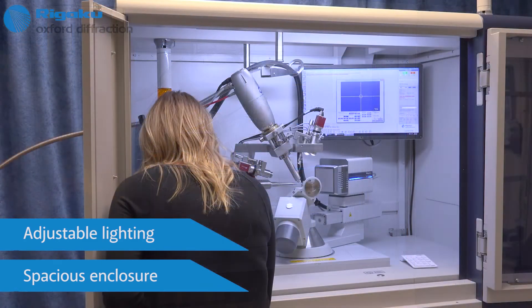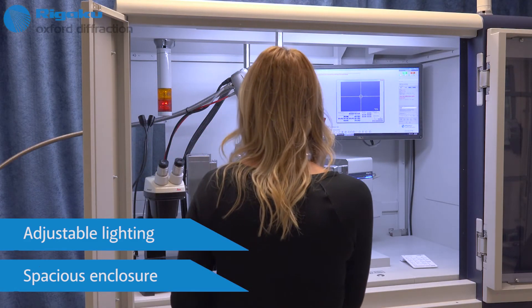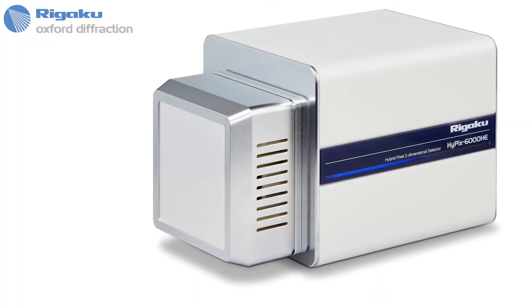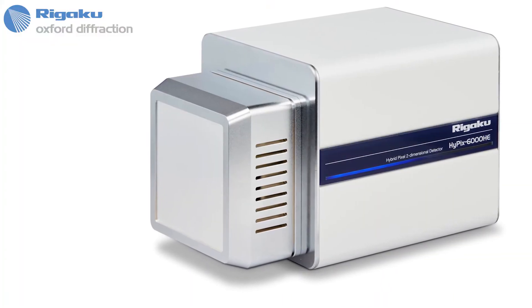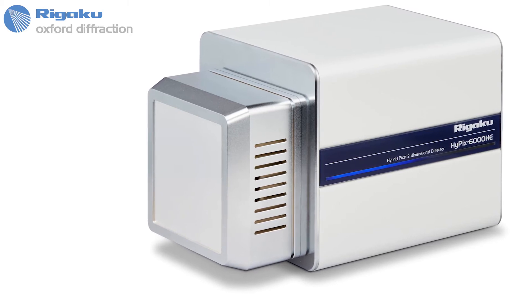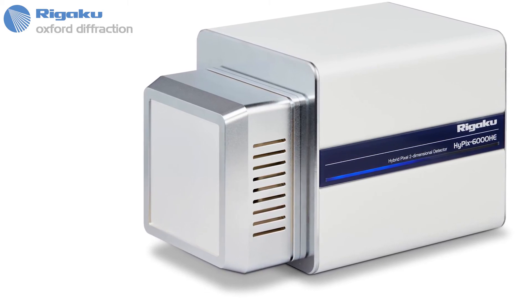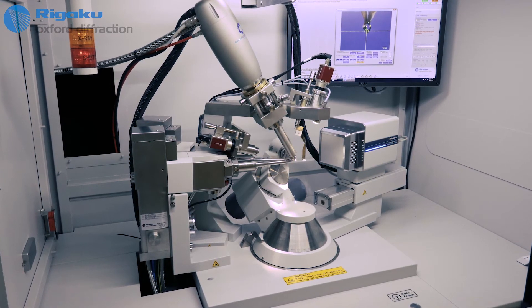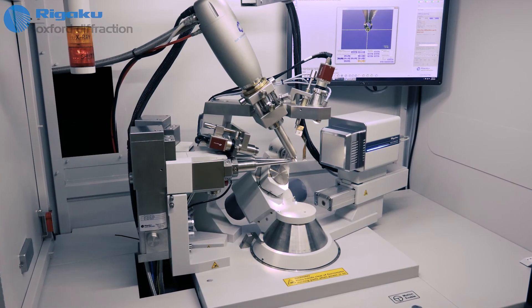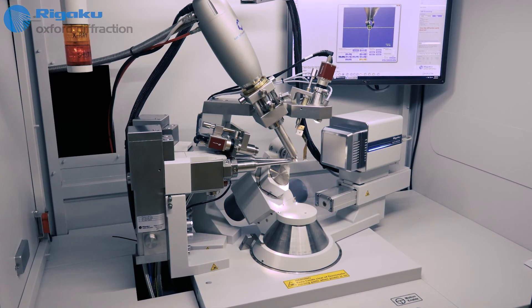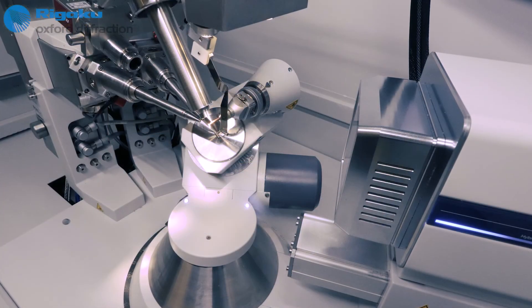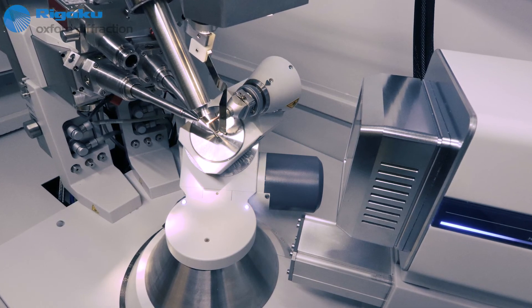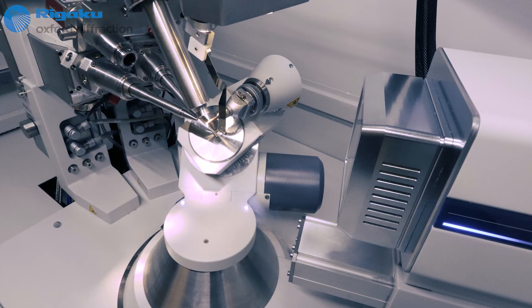Rigaku's XtaLAB Synergy systems are equipped with a hybrid photon counting detector, the HyPix-6000HE, which combines small 100 micron pixels with a zero dead time mode and a lightning fast 100 Hz frame rate, providing the user with the ability to resolve large unit cells easily, as well as to perform the most accurate shutterless data collection.